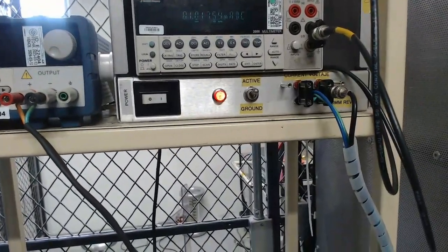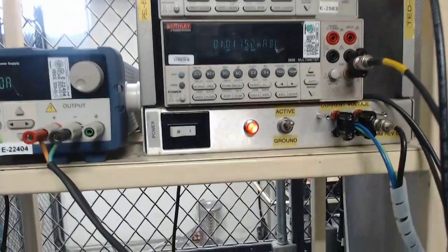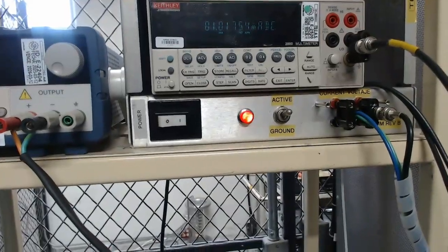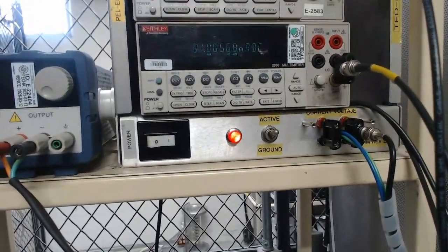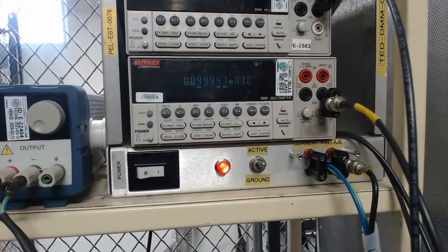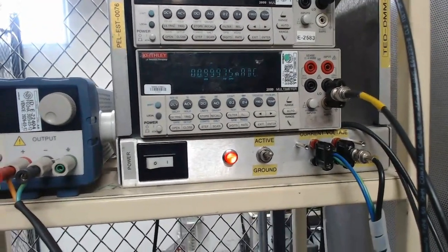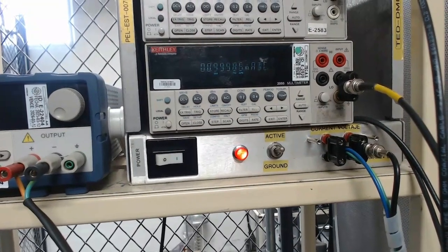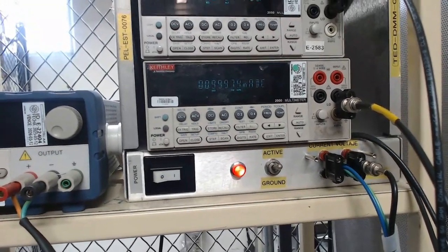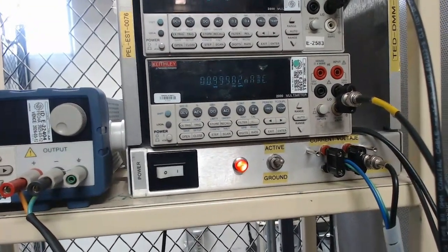After that, output voltage is adjusted to achieve 1 milliamp of output current. Value in the DMM is centered as much as possible. In this case, to 1.000 milliamps. After the current value is achieved, the test point DMM is used to measure the voltage at TP7 of the Micro-X control board.